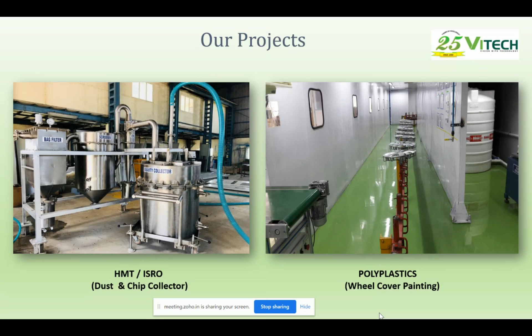You can see the dust collectors we are using also have to be maintained properly. How do you measure the dust, whether the filters have to be replaced, whether it is working effectively? We provide proper manometers to measure the pressure differential across the filter. We have a set limit for the pressure drop, and when the filters are choked, the pressure across the filter will definitely increase. Then we get a signal that the filters have to be replaced or cleaned. So this type of instrumentation and automatic systems are provided.